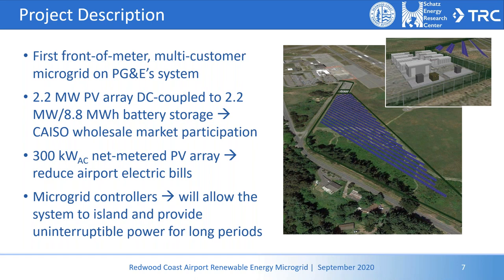So those 20 accounts have a peak demand of about 330 kW. We're about 2.5 megawatts if you add the DC coupled plus the net metered system. So it's really quite large with respect to the loads on the microgrid circuit. We're using it during normal grid-connected operation to participate in the wholesale market, and that's why it's sized that way.